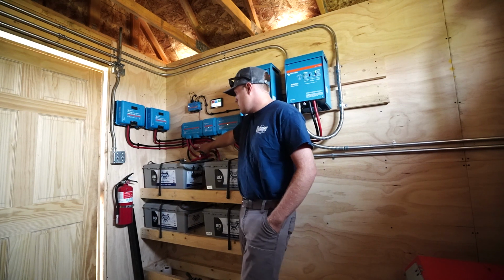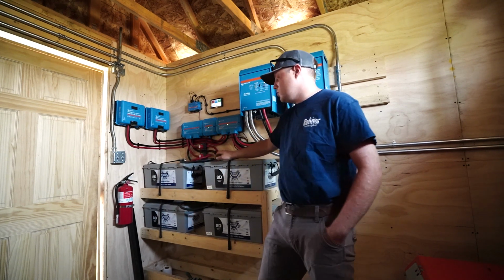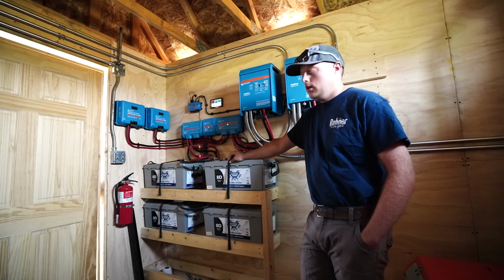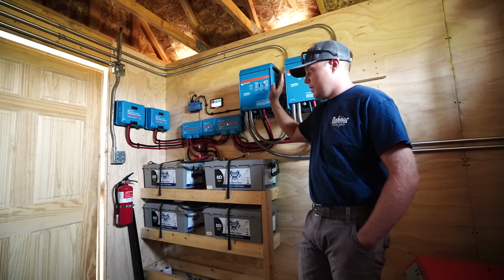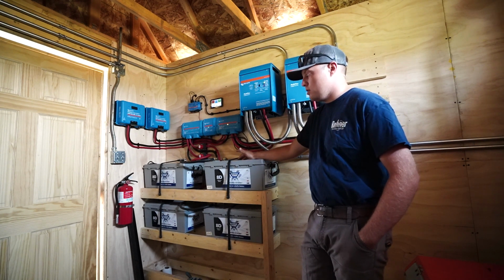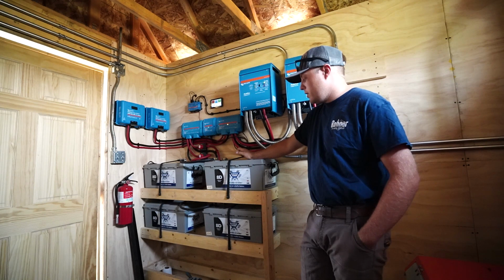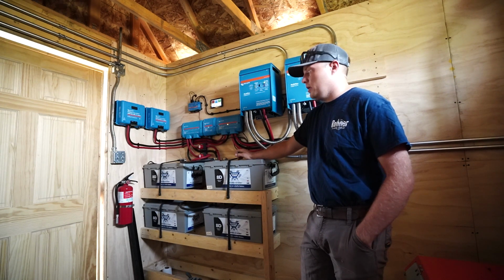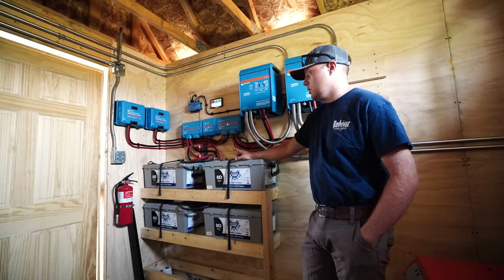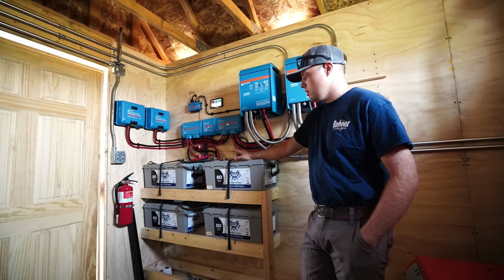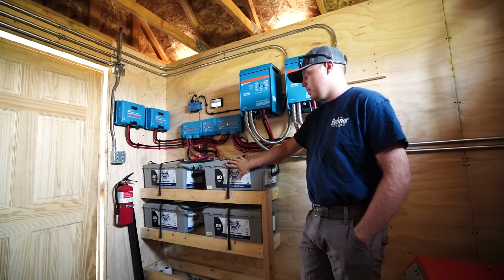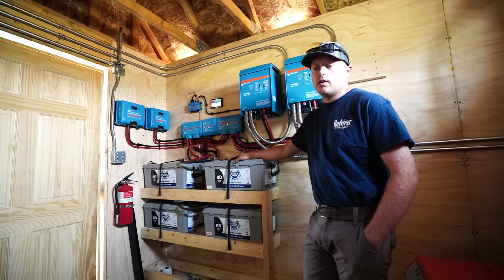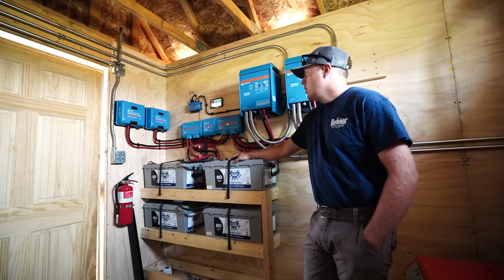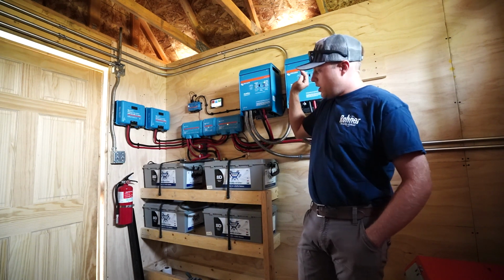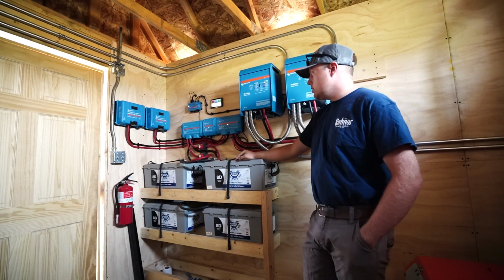We have a couple of battery disconnects here. This allows us to turn off and on our batteries, shut the whole system down if we needed to do maintenance. They're 12 volt batteries, 270 amp hours, but it's a 24 volt system. So the top 2 batteries are in series, the bottom 2 are in series, and then the battery sets are wired in parallel.